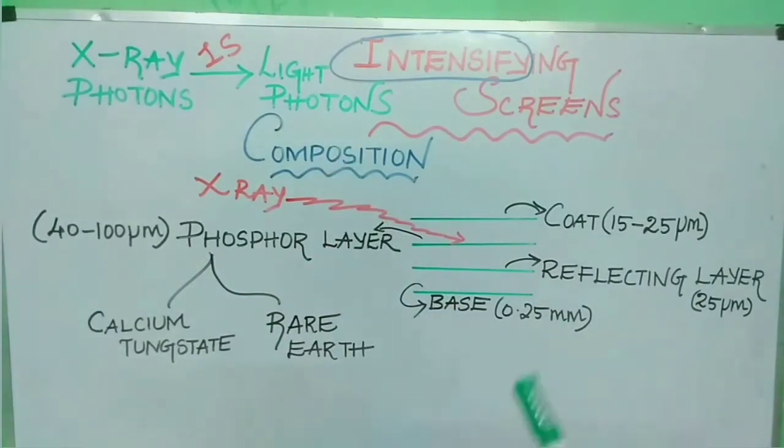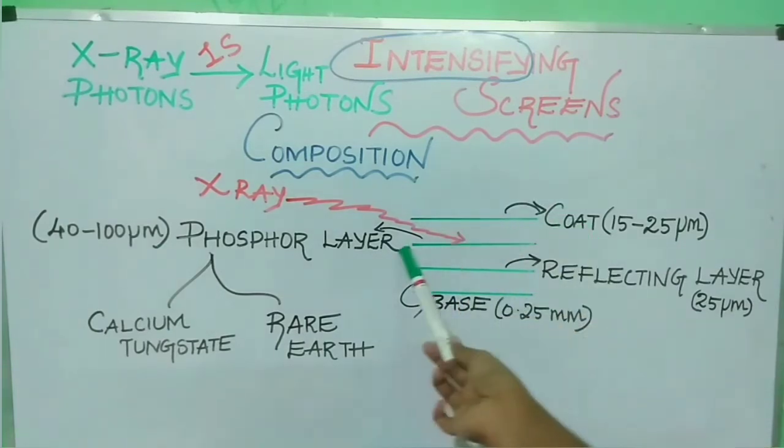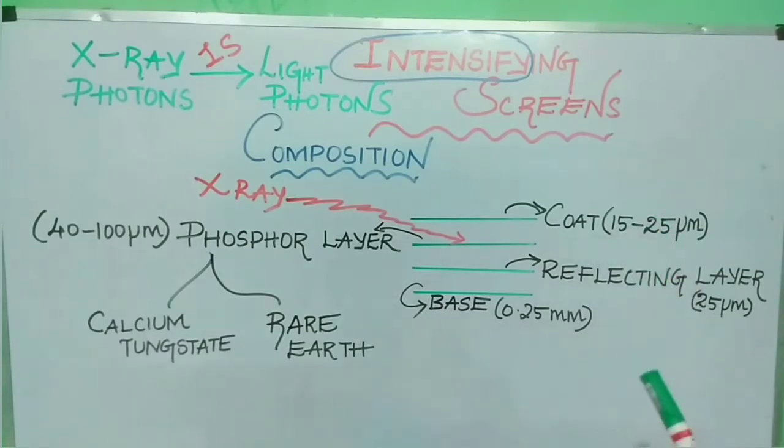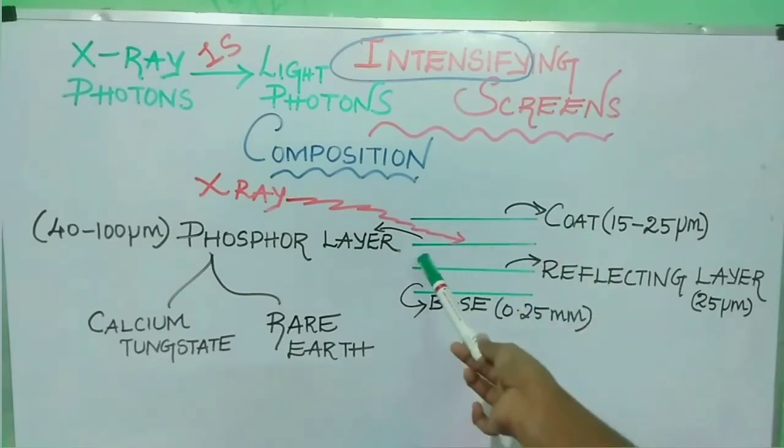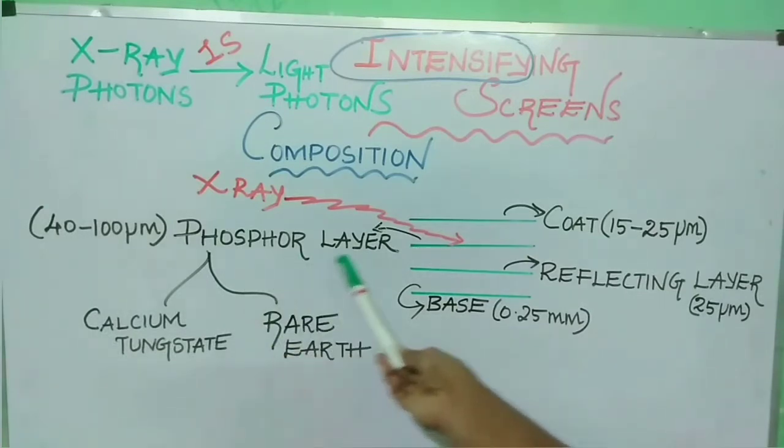Now let's study about the components of an intensifying screen. It has coat, phosphor layer, reflecting layer and base. This coat is about 15 to 25 micrometers in size and protects the phosphor layer from mechanical insults. This coat is made up of plastic, largely composed of cellulose. Cellulose is a wood-based bioplastic made from trees and can be mixed with a polymer.